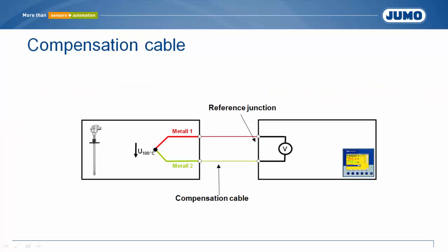As described, a second thermoelectric voltage arises at the device. Internal temperature compensation takes place by measuring the temperature of the reference junction. For the internal temperature compensation, it is important that the thermocouple is extended with the wiring. The wiring material corresponds to the material of the thermocouple. If the material exactly corresponds to that of the thermocouple, this is called thermowire. In the case of substitute materials, which have the same thermoelectric behavior, the wiring material is called compensation cable.